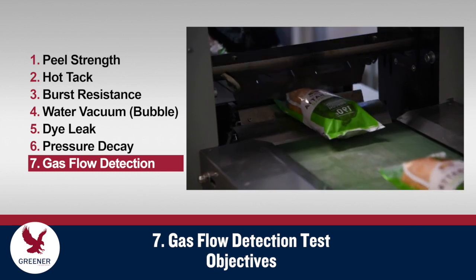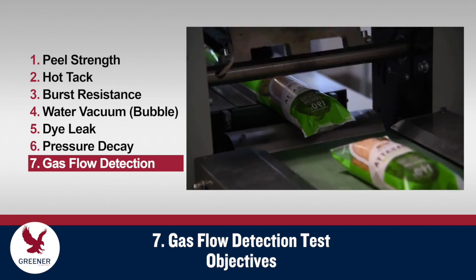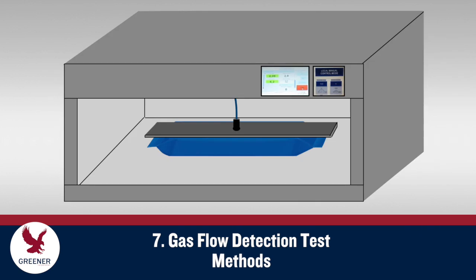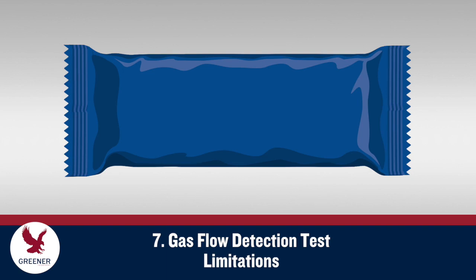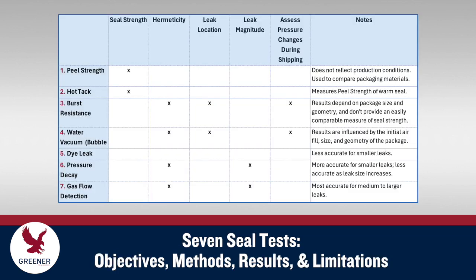Gas flow detection tests also measure the presence and magnitude of leaks. A package is inflated or evacuated with a needle probe, and the device monitors the gas flow required to maintain a set pressure level. Any gas flow required to maintain a given pressure indicates the presence and magnitude of leaks. Since pressure levels produced by gas flow detection devices are limited, accuracy is best for medium to larger sized leaks. This summary chart will help you compare all seven seal tests.